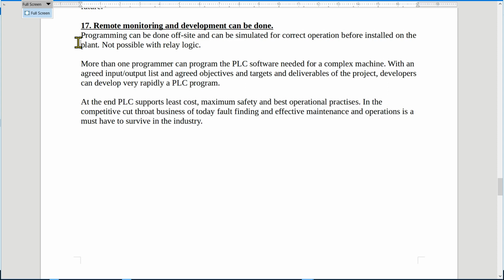And when there is time available, when a machine is down, for example, you will reload your program that is simulated and tested, and you can then verify the operation of the machine. In case there are any unforeseeable incidents, you can wipe out your new program very easily by restoring the backup program and reloading the original program without affecting production. Now, this cannot be done with relay logics.